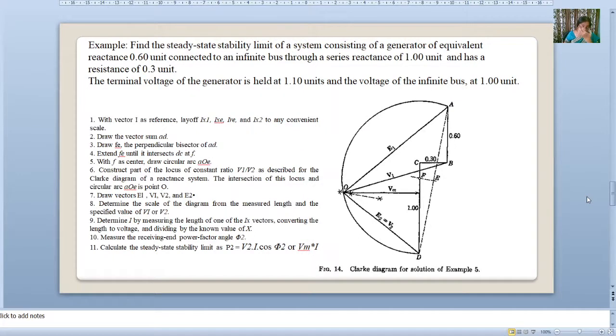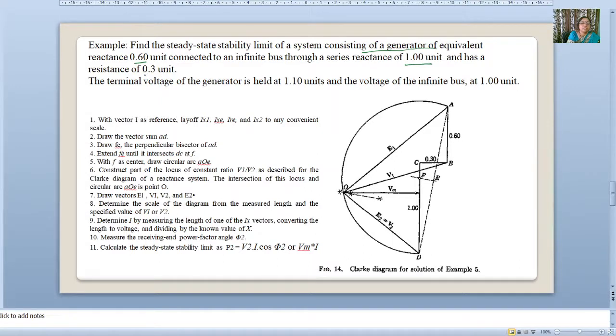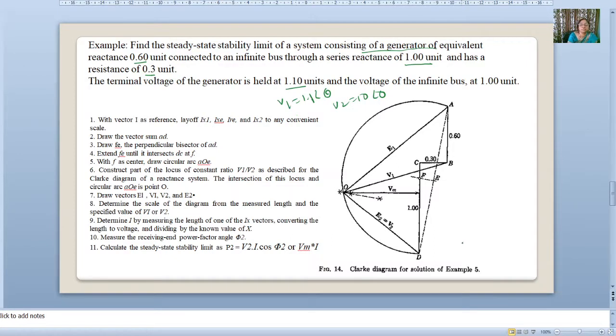Now this example you have to solve on graph paper. Find the steady-state stability limit of a system consisting of a generator of equivalent reactance 0.6 unit, connected to the infinite bus through series reactance of 1 unit and resistance of 0.3 unit. The terminal voltage of the generator V1 is 1.1; infinite bus V2 is 1.0 at angle 0; V1 is 1.1 at angle θ. This example is the same as in lectures 7 and 8, with resistance 0.3 added.